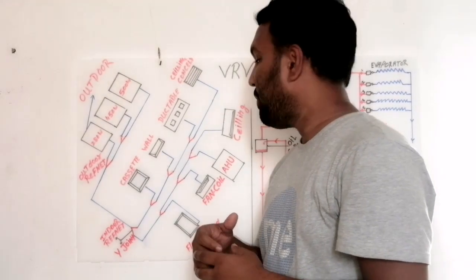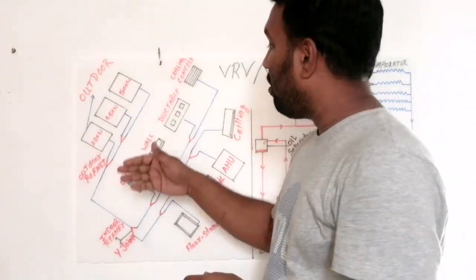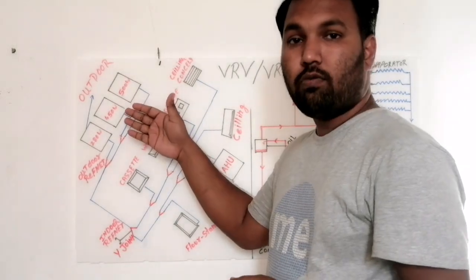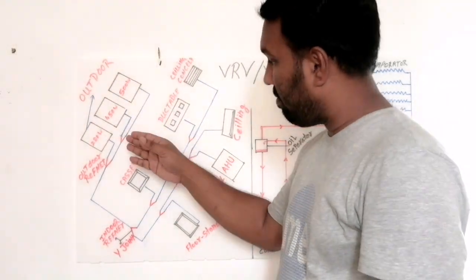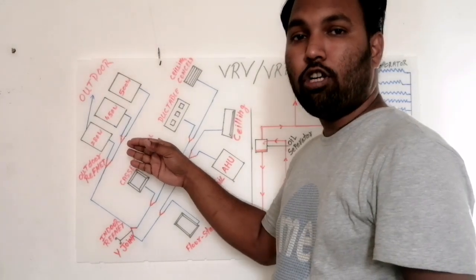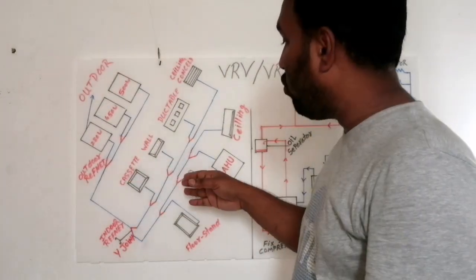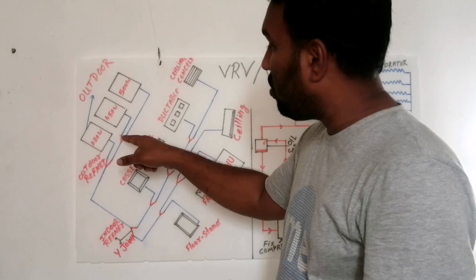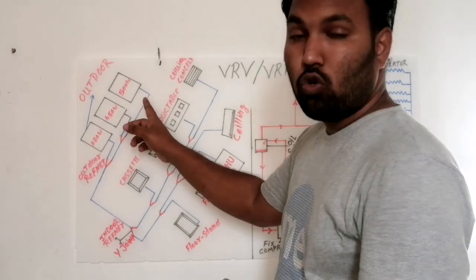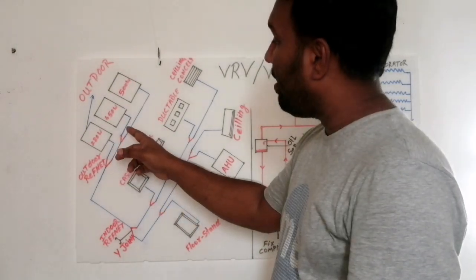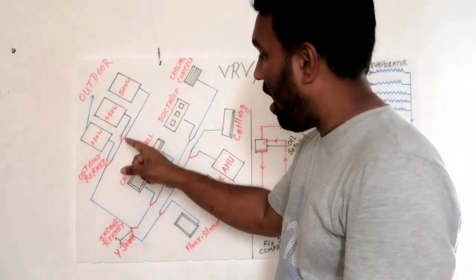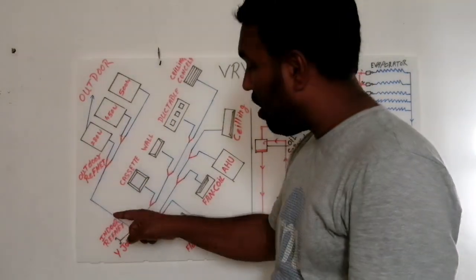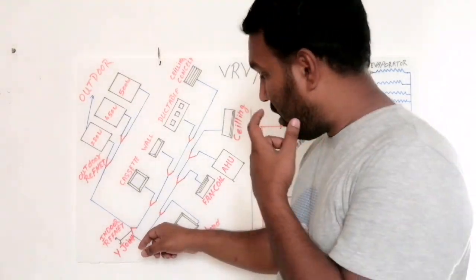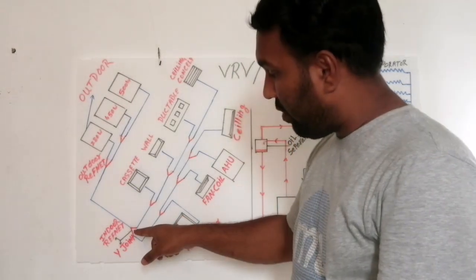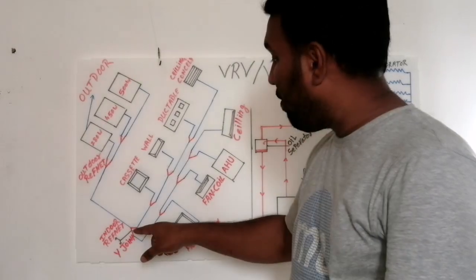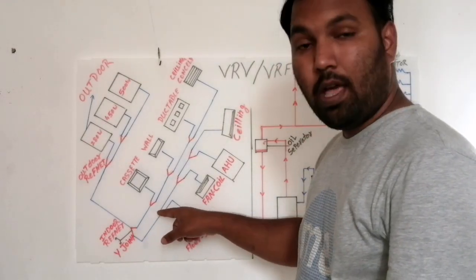The placement of the Y joint is also different. Near the outdoor unit, if we have to increase the outdoor units, the position of the Y joint, ref net or distributor will be different compared to the indoor. As you can see, the two mouths are placed towards the outdoor, which means on the front side we can increase our outdoor quantity, and on the back side there should be only one single pipe which comes to our indoor ref nets. This is the indoor ref net, which is the first ref net of our indoor. From here it is divided into two pipes.